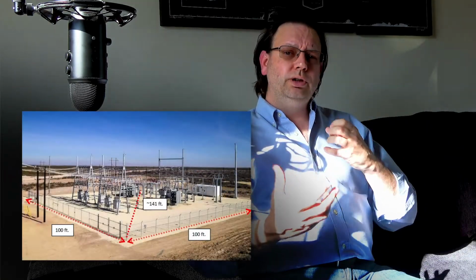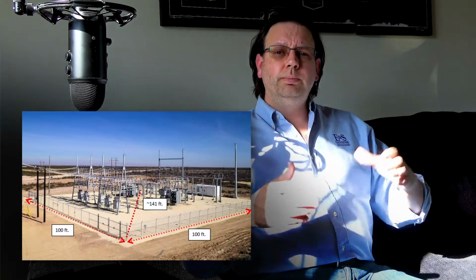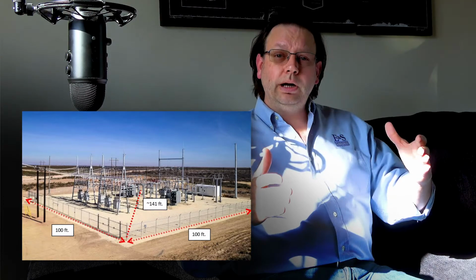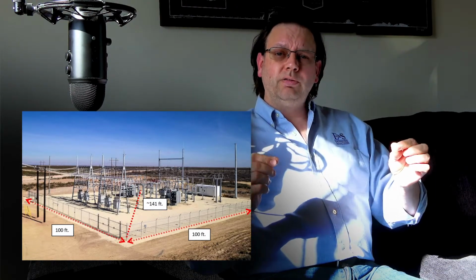Well, stretching a wire from your grounding system you want to test to the other side of the planet is something less than convenient, right? It's pretty hard to get to the other side of the planet with a wire, right? So what we say is 10 times our sphere of influence is good enough. You take the size of your grounding system, and you take the maximum diagonal length, and in the case of what we've been using commonly in these videos, a 100 foot by 100 foot substation grounding grid, the diagonal distance is going to be about 141 feet, so we can say 150 feet. So we want to say that one sphere of influence is 150 feet. So we want to be 10 times that distance away from it.